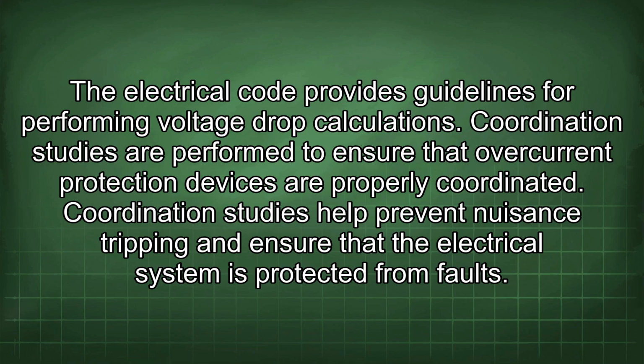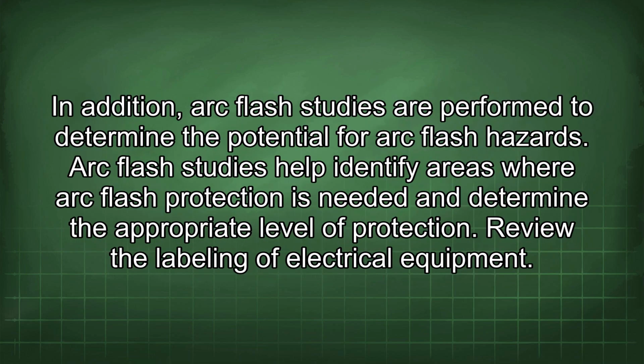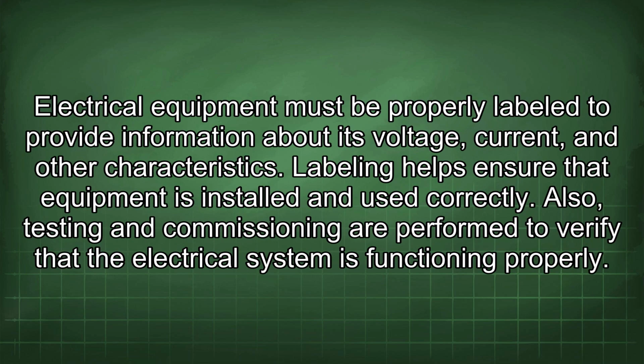Coordination studies are performed to ensure that overcurrent protection devices are properly coordinated. Coordination studies help prevent nuisance tripping and ensure that the electrical system is protected from faults. In addition, arc flash studies are performed to determine the potential for arc flash hazards. Arc flash studies help identify areas where arc flash protection is needed and determine the appropriate level of protection. Review the labeling of electrical equipment. Electrical equipment must be properly labeled to provide information about its voltage, current, and other characteristics. Labeling helps ensure that equipment is installed and used correctly.